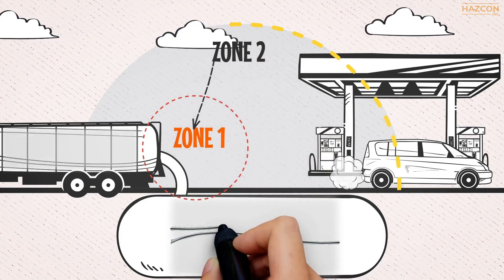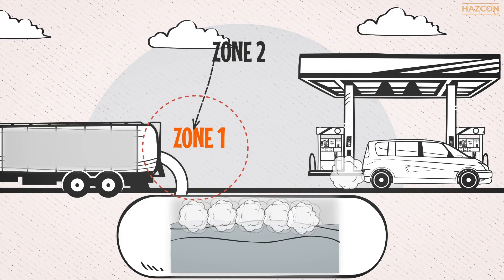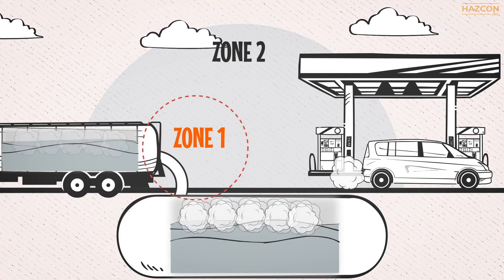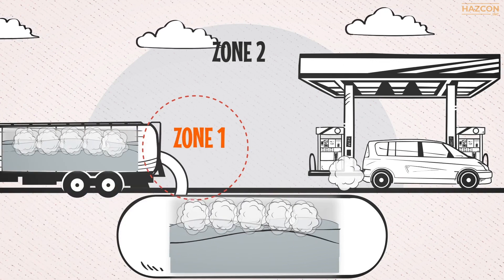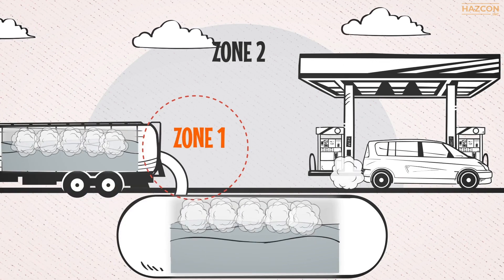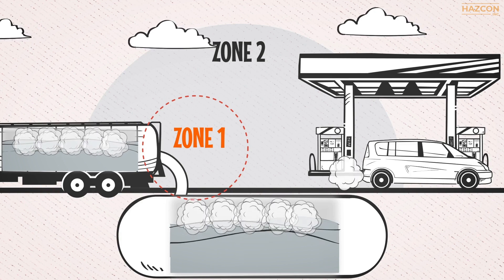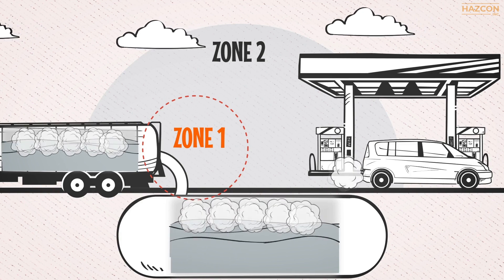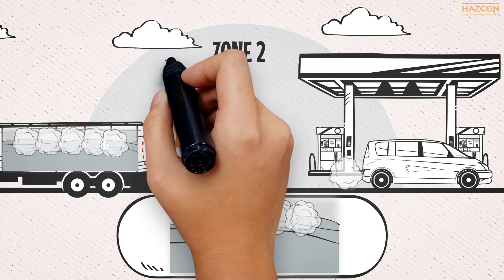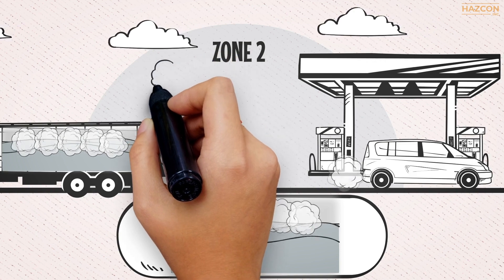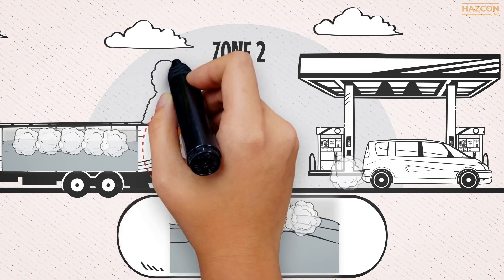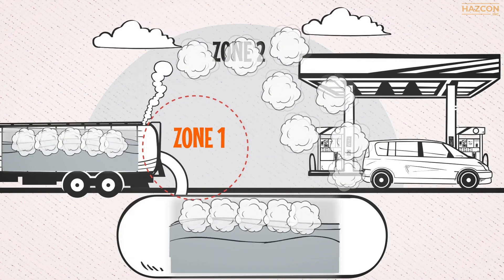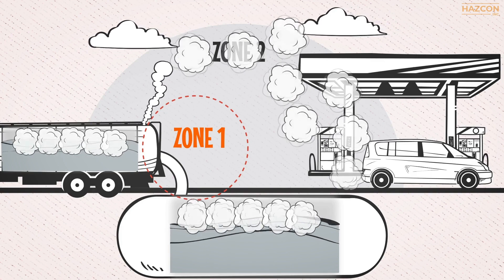In our example of the tank, the area identified as Zone 2 is outside of and immediately adjacent to the Zone 1 area. Under normal operating conditions, there would be no gas present outside the tank. If gas leaks out of the tank due to accidental rupture, repair, or maintenance, however, a hazard exists.